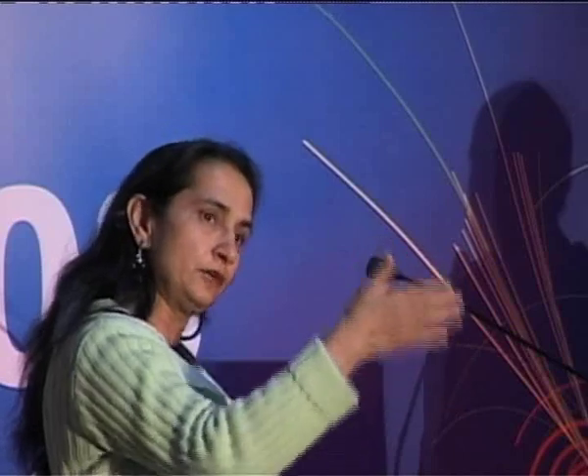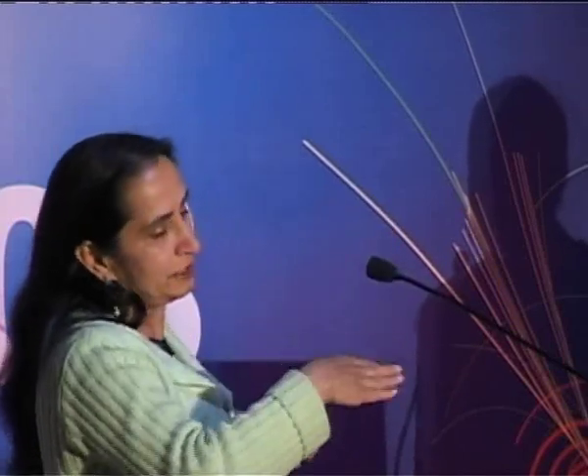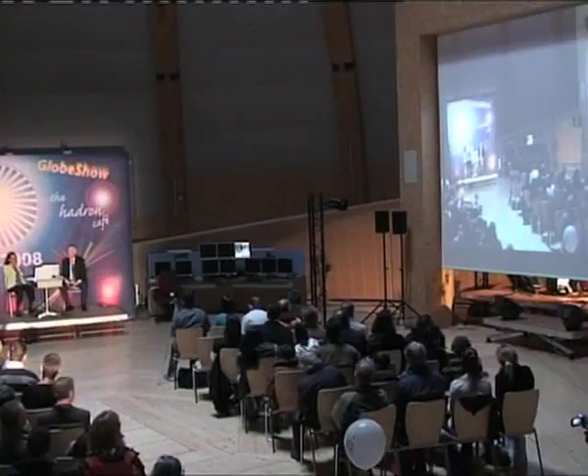We accelerate protons in an accelerator and we fire them at a tumor. But what happens then? So the protons pass through the body and they only deposit the energy at the tumor, is that right? The reason is because protons are quite large compared to the matter they're passing through, which is mostly electrons. So they deposit their energy at one point called a Bragg peak. So most of the energy is deposited exactly where you wanted to have it deposited. If you want it further in, you can accelerate them faster. If you want them slightly further towards the surface, you accelerate them a little bit less. So you can deposit them exactly where you want.